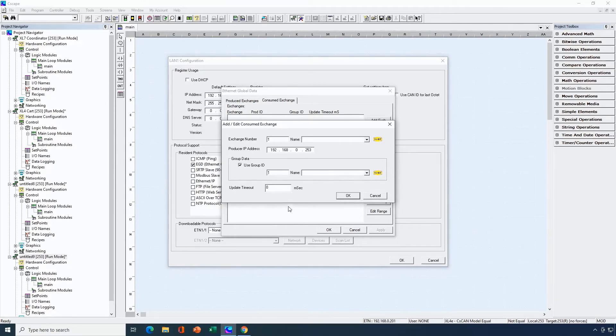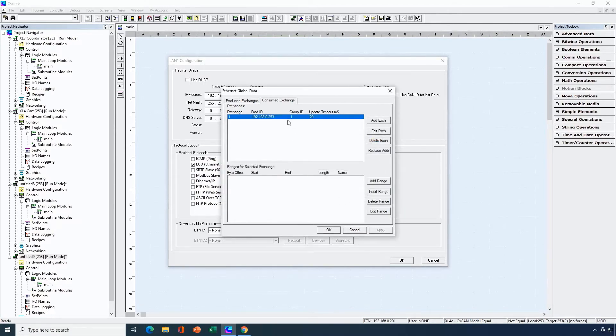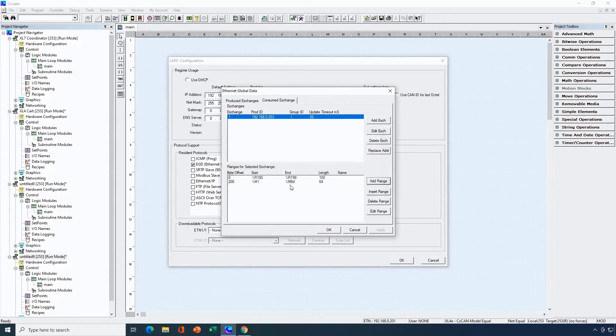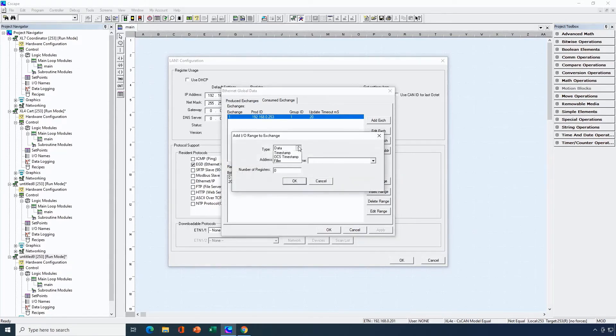Now I have to set a timeout. It's sent every 10ms so let's set this to 25ms — it will still come in every 10ms but it's not going to be late until it takes longer than 25ms to arrive. That's my consumed exchange complete. Now let's add a range of data. There were 100 words of register data so I'll map those in, and I can map them into an independent location in memory — I'll map that into R100 locally. I'll add those bit types and put them right at the very beginning — again 64 bits. Then let's add status, because it's important that we have status on the receiving side especially, to tell us if the data we're expecting did not arrive.